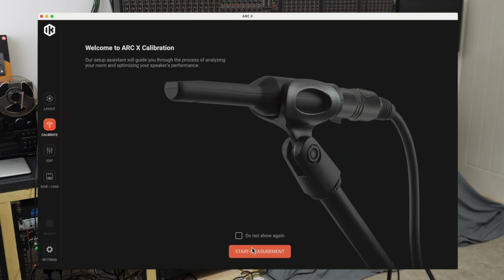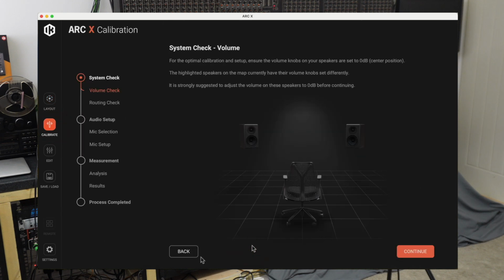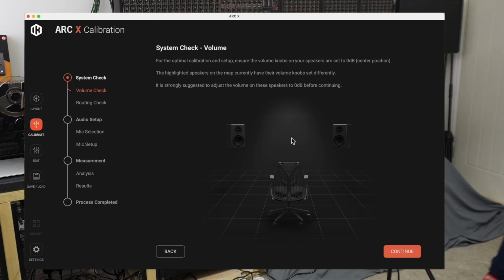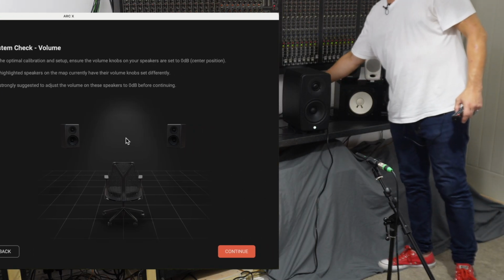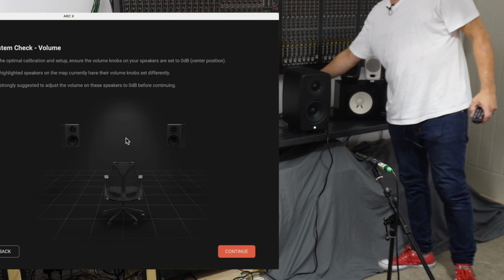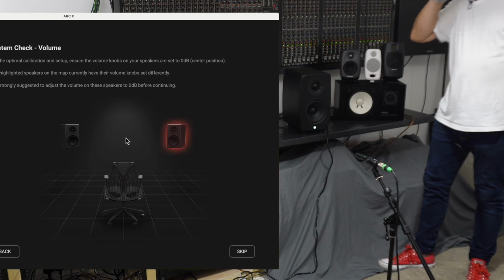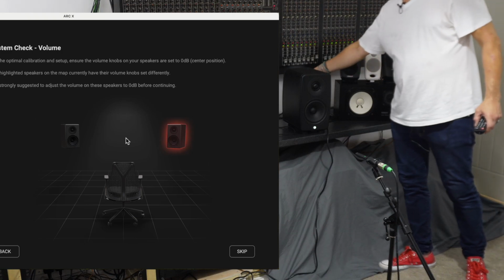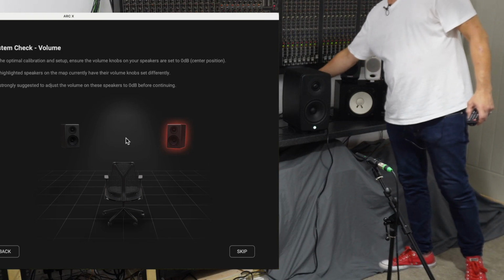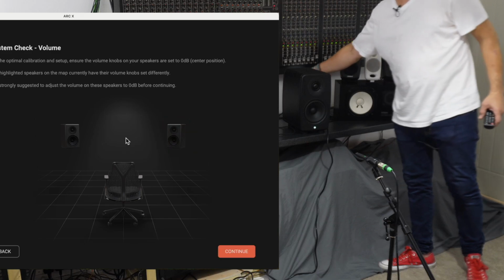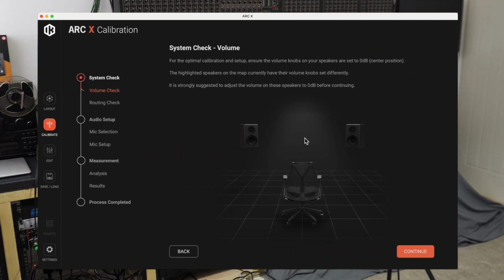Calibrate. Start measurement. Now the first thing you're presented with is this image, and if one of the monitors is not set to its 0 volume position with the rear volume control, then it will be orange like that. So if either monitor is not set to 0, you go around to the back and adjust the volume control back to the 0 position, which is really easy to do because it's very heavily center detented, so it's easy, look, click, and it's back to 0. Okay, that's that. And then we go to continue.